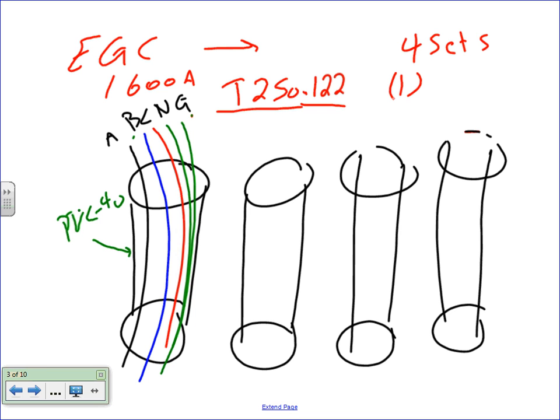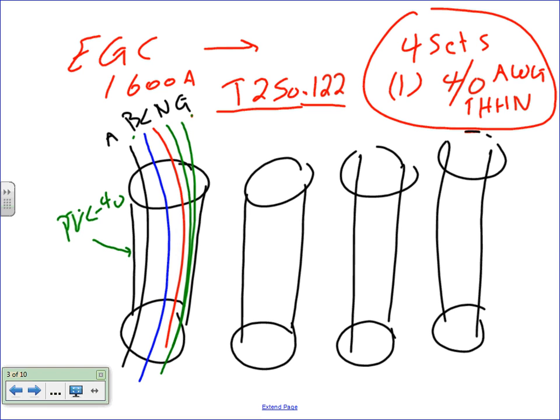And if you go there to size an equipment grounding conductor, guys, we're going to end up with four sets of one conductor. Each one of them is going to be 4/0, if I did that right, 4/0 AWG THHN, green. To size the equipment grounding conductor, why four sets? The code says if you are paralleling it, you have to run a full set in each one of them. If you're paralleling the phases in a neutral, the equipment grounding conductor has to be a full set in each one of them. These are not parallel. A full set in each one of them. Yes, sir.